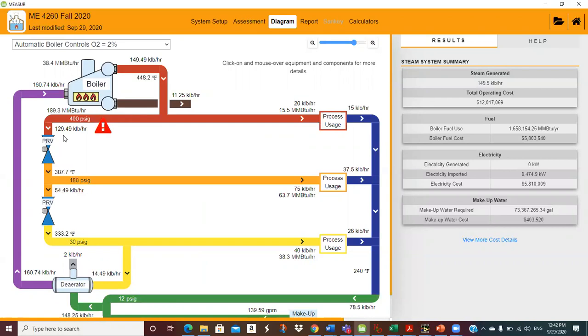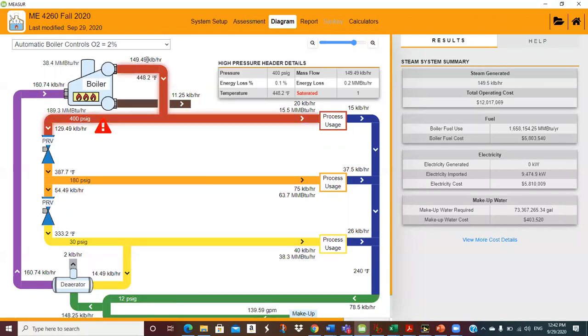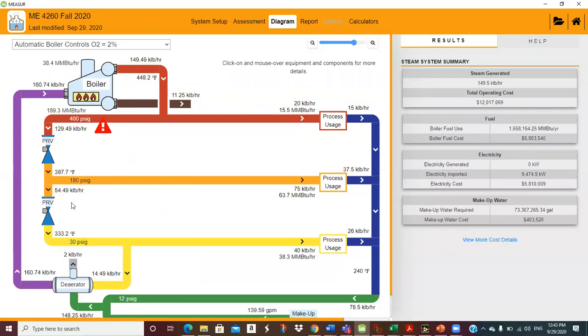You do have different control modes. What you really want to do is just balance the header — instead of putting steam through the PRV. Up here, I've got almost 130,000 pounds an hour going through a PRV. That's a lot of exergy destruction — I'm throwing away the potential to put that through a turbine and turn a pump, an air compressor, or a generator and get some useful energy out of it.